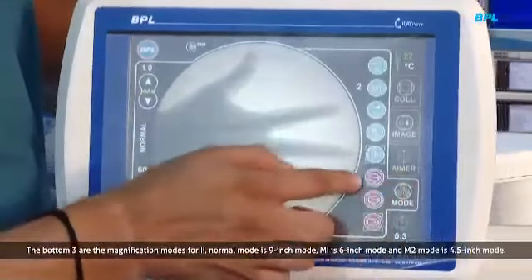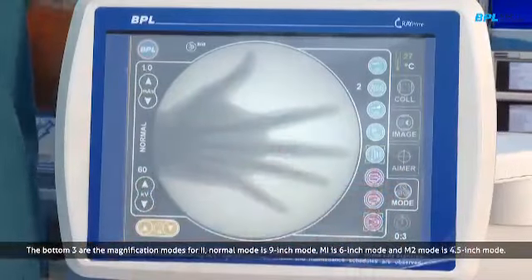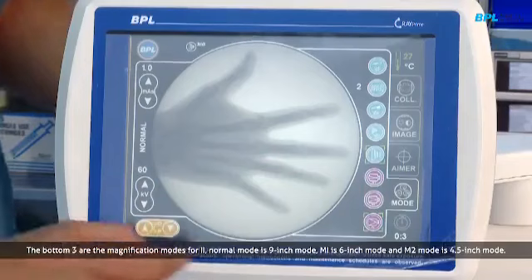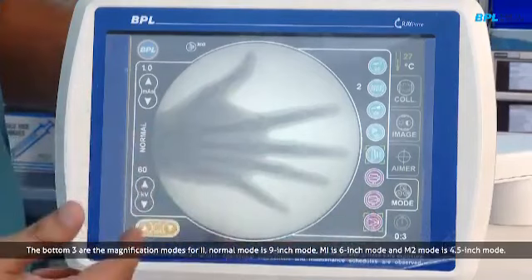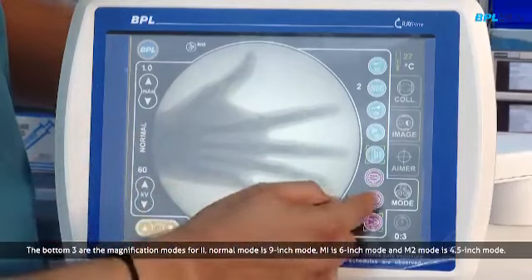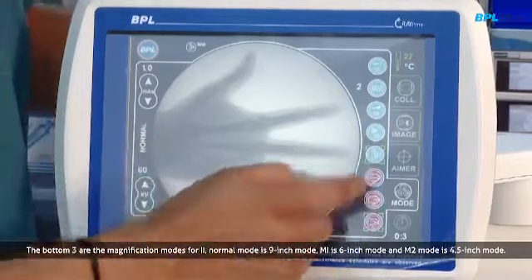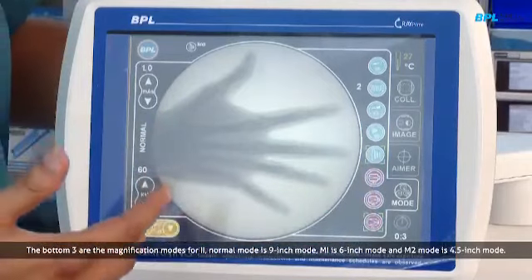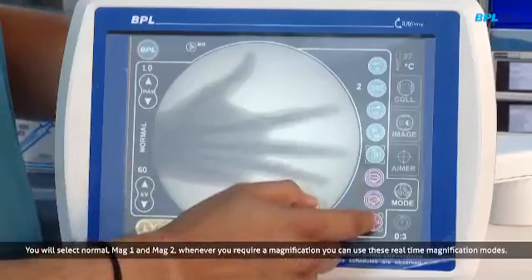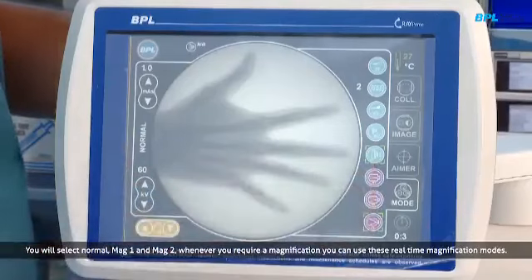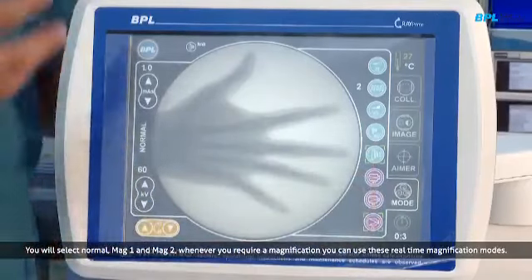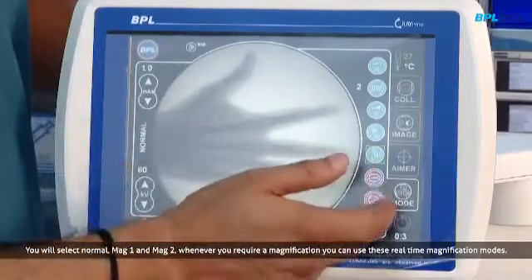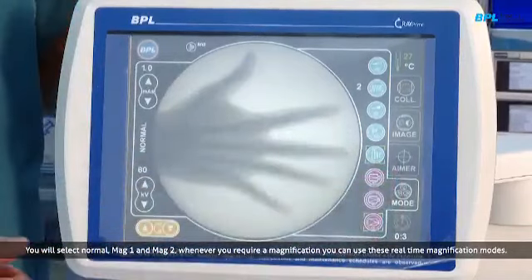And the bottom three are the magnification modes, which are for the II. So the normal mode is the 9-inch mode, the M1 mode is the 6-inch mode, and the M2 mode is the 4.5-inch mode. You will select normal, Mag 1 and Mag 2. So whenever you require magnification, you can use this real-time magnification mode.